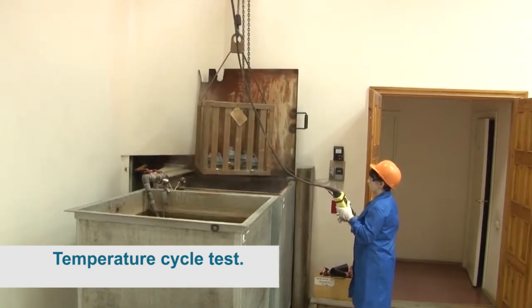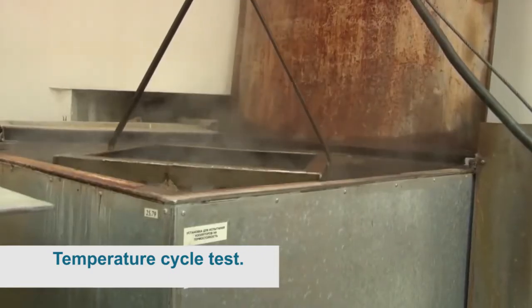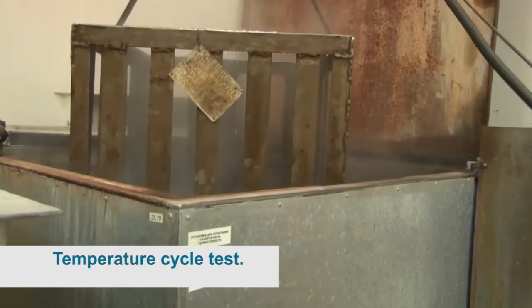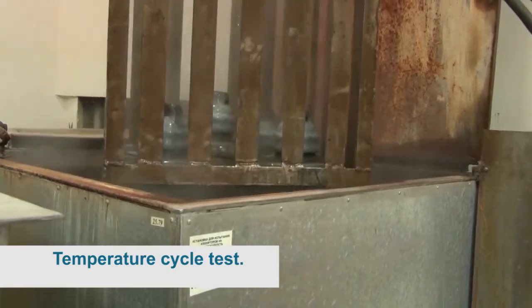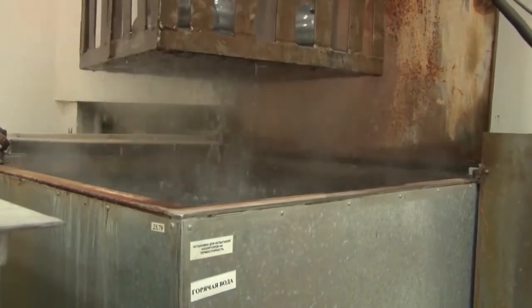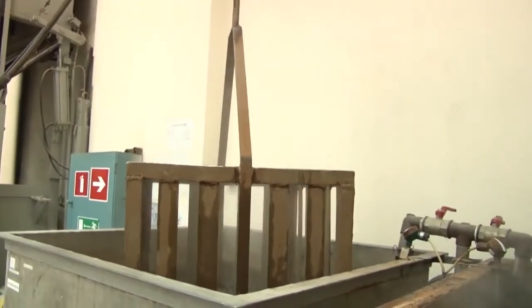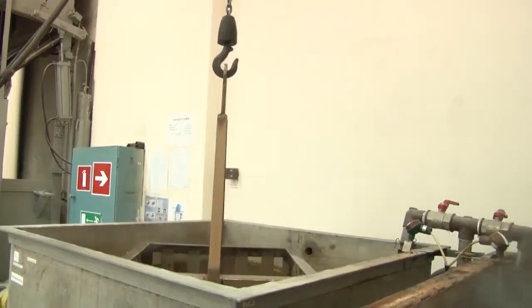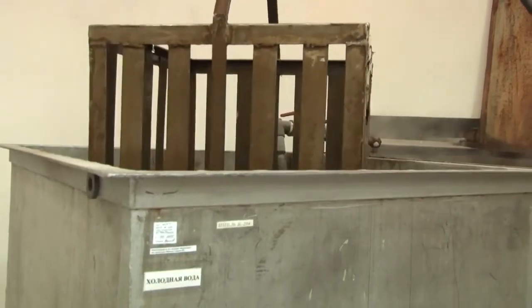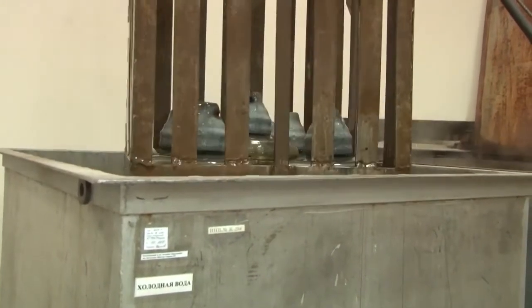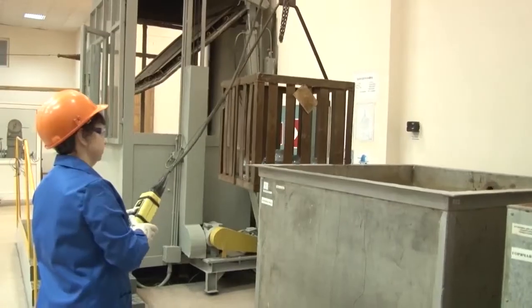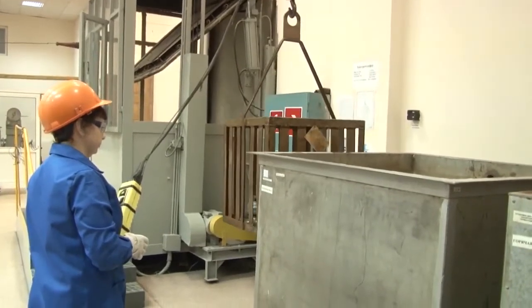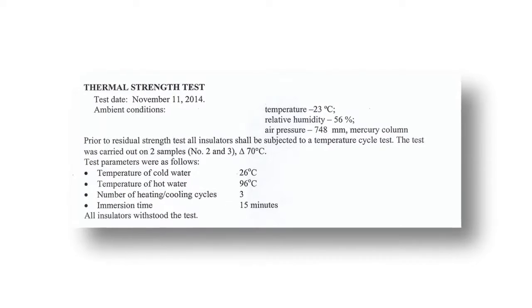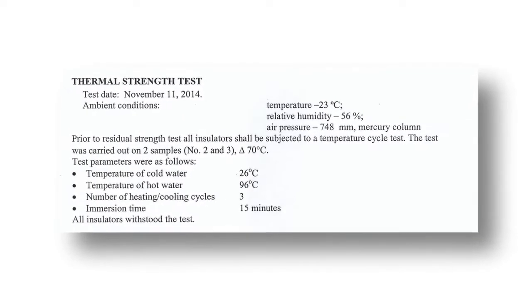Temperature cycle test. Insulators of type PS12A and PS70E have been subjected to the 3-stage heating and cooling cycles with a temperature drop of 70 degrees Celsius. The insulators had been submerged in cold water and hot water bath for 15 minutes. As a result, during the visual inspection, no cracks or fractures in the cement joint of the insulators were revealed. The insulators meet the IEC requirements.